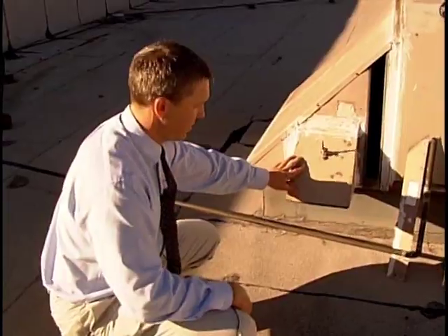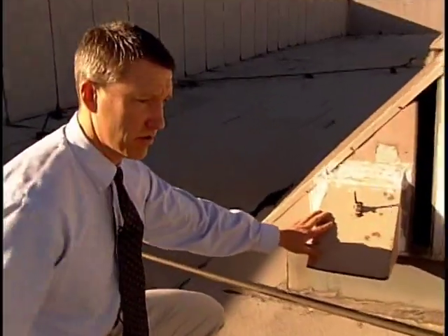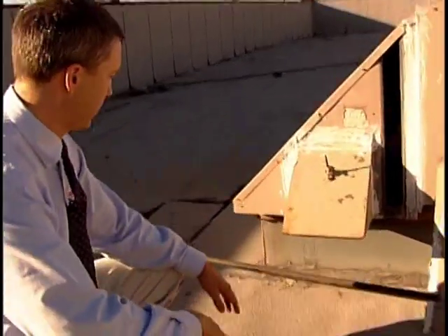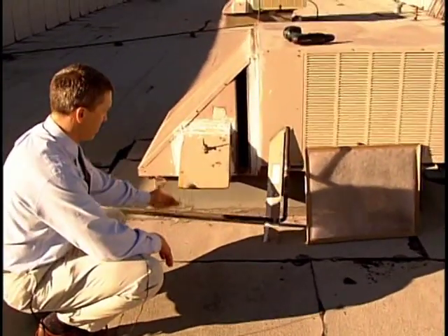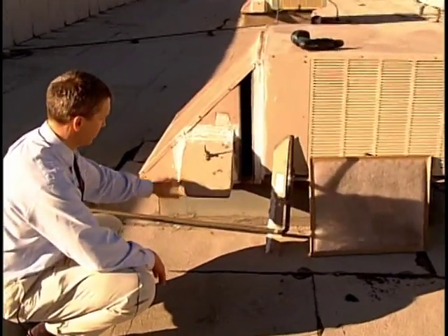This is our fresh air inlet. We want to make sure and take a look at our surroundings, make sure there isn't any puddles accumulating, birds nesting, things of that nature that might be sucked into our office environment. Air-conditioned buildings are, especially in the modern building, finely tuned. It takes a lot of effort to make sure you got enough air coming out of these delivery systems in certain areas to keep everybody happy and to keep the airflow, the volume going through.